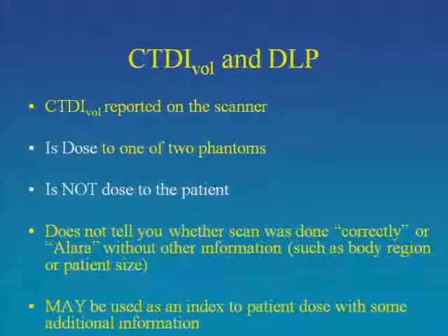No, okay. So let's talk a little bit about CTDIvol and DLP and see what they tell us. It is dosed to one of two phantoms, either the 16 or 32 centimeter. It is not dosed to the patient.